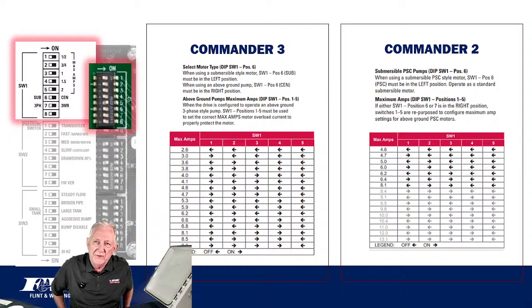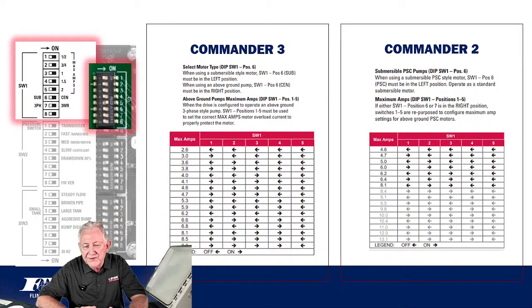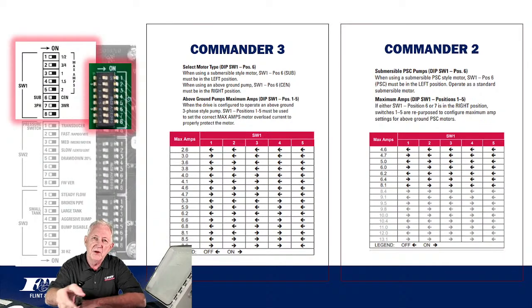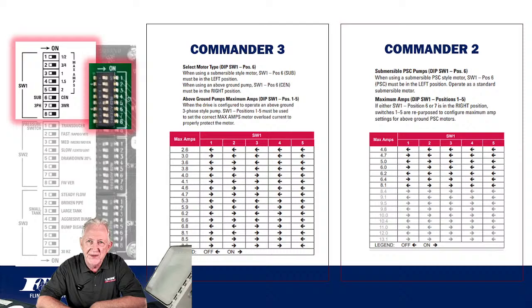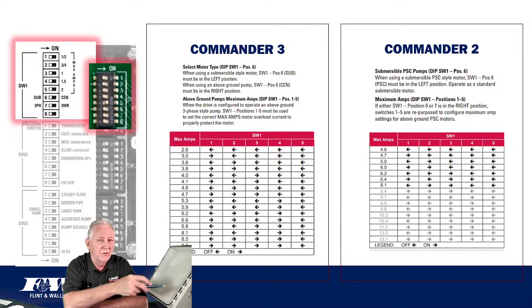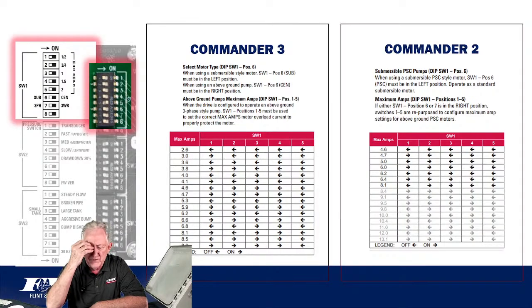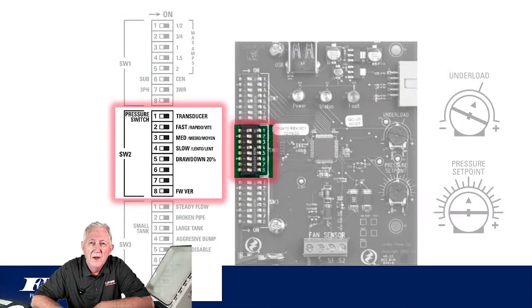And same thing with the Commander 2. So basically, if it's a submersible motor, we'll go ahead and set it based on horsepower. However, if it's going to be a centrifugal motor, we're going to base that on max motor amps. And that's also where you're going to see that PSC label. That stands for permanent split capacitor. So this will also operate a centrifugal motor with a permanent split capacitor in it.